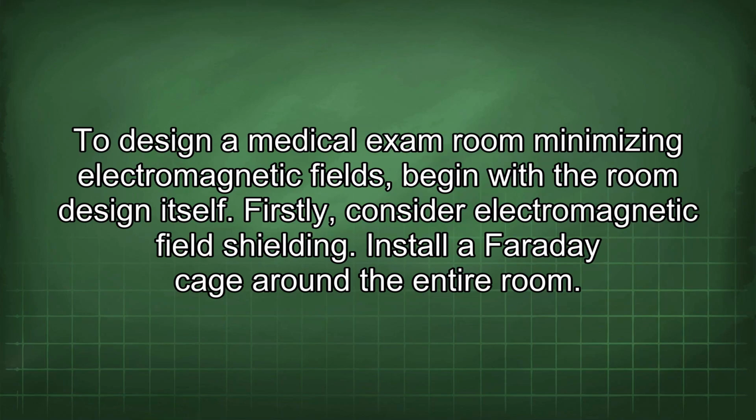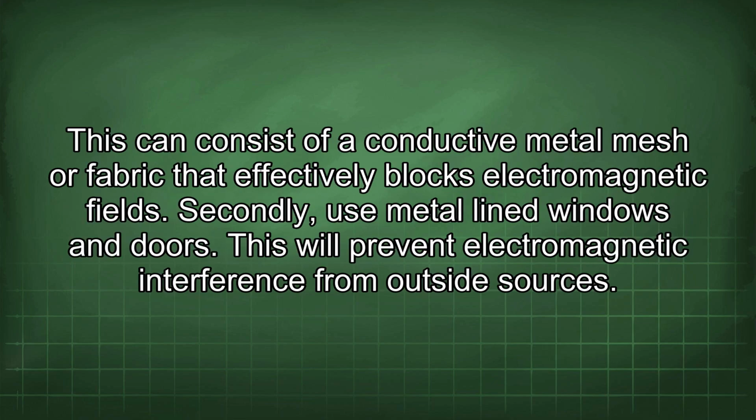To design a medical exam room minimizing electromagnetic fields, begin with the room design itself. Firstly, consider electromagnetic field shielding. Install a Faraday cage around the entire room. This can consist of a conductive metal mesh or fabric that effectively blocks electromagnetic fields.